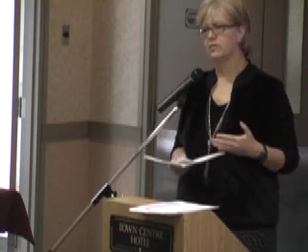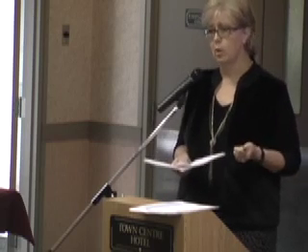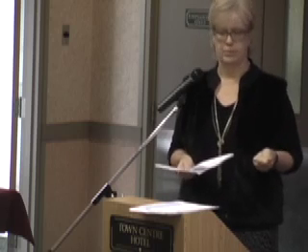And what that tells us, it allows us to find what we call nested outages. So often in storms or in poor weather, we'll have multiple breaks of our line. And so today, the crews fix the power, they see the porch lights are back on, they drive back. And there's still a nested outage. We'll get a call 4 hours later. When are you guys coming to fix my power? Only then we know that there's still more premises out.